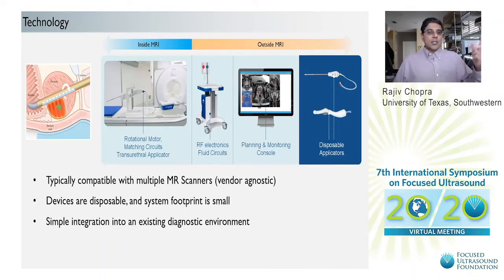So what is the general technology for an MRI-guided minimally invasive focused ultrasound procedure? Well, in the case of this particular technology, which is the transurethral ablation of the prostate, it involves disposable applicators, as you can see here on the right. In this case, one to go into the urethra to locate transducers at the prostate, and one to go in the rectum for cooling. That's a unique piece of this technology, or all these technologies, which is a disposable device. The devices are inserted usually in the MRI room or adjacent to it, and then attached to some delivery system. In this case, there's a rotational motor that allows precise positioning and rotation of the device during treatment. There's some electronics, some matching circuits here. And this is inside the MRI.